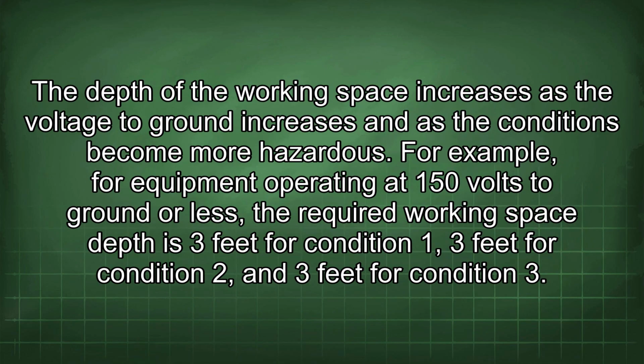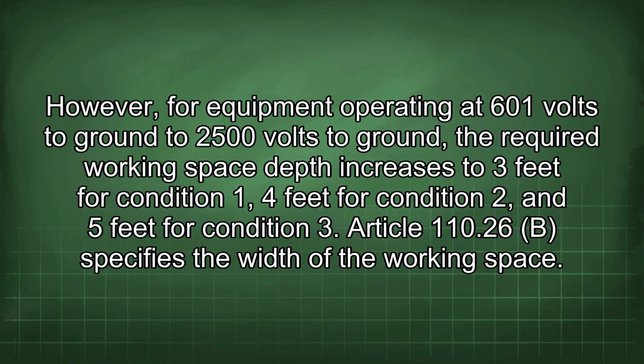The depth of the working space increases as the voltage to ground increases and as the conditions become more hazardous. For example, for equipment operating at 150 volts to ground or less, the required working space depth is 3 feet for condition 1, 3 feet for condition 2, and 3 feet for condition 3. However, for equipment operating at 601 volts to ground to 2500 volts to ground, the required working space depth increases to 3 feet for condition 1, 4 feet for condition 2, and 5 feet for condition 3.